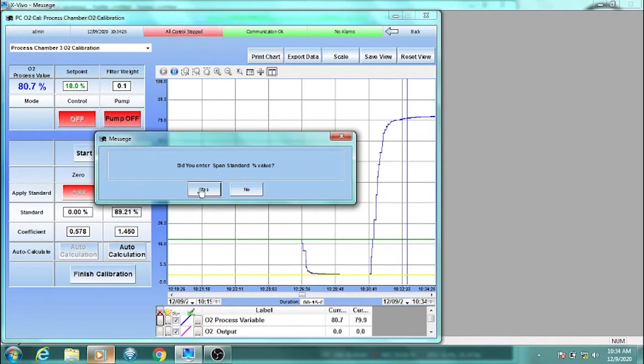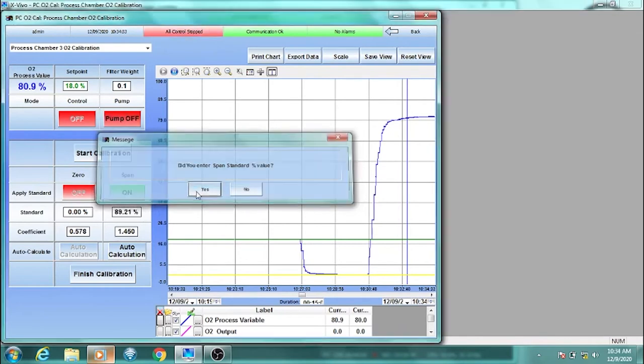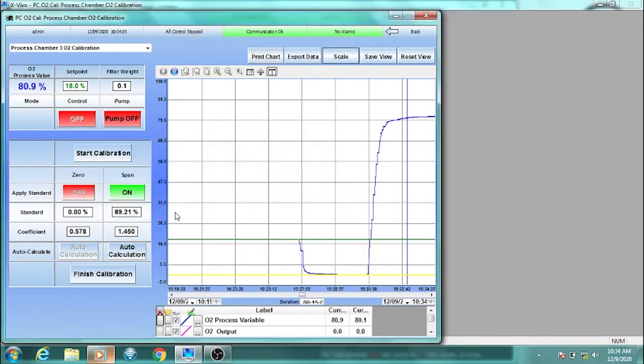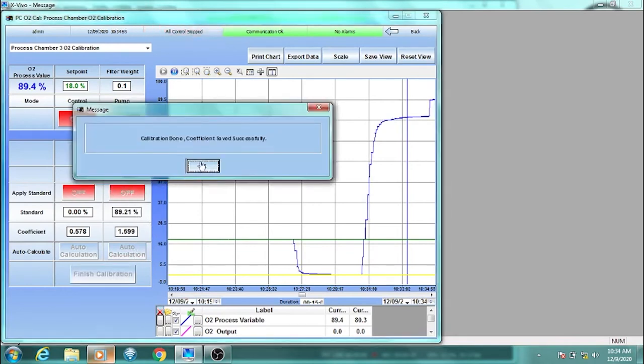The software will ask you if you entered the span standard percent value. This is what we changed earlier, so you can click Yes. Wait a few seconds and make sure the value is adjusted to a reading within plus or minus 0.1 of the standard percent. If the reading starts to drift after being adjusted, your oxygen sensor's health may be starting to decline. Turn span calibration off. Click Finish Calibration. Confirm the coefficients were saved successfully by clicking OK.